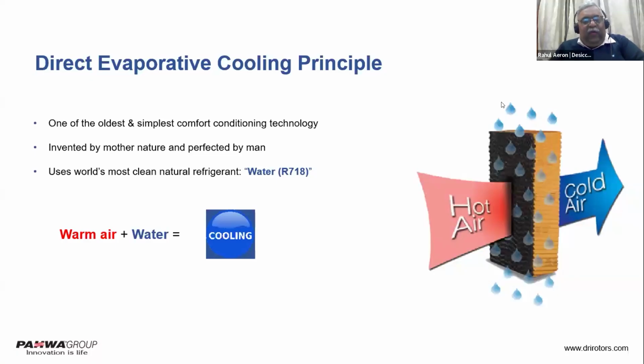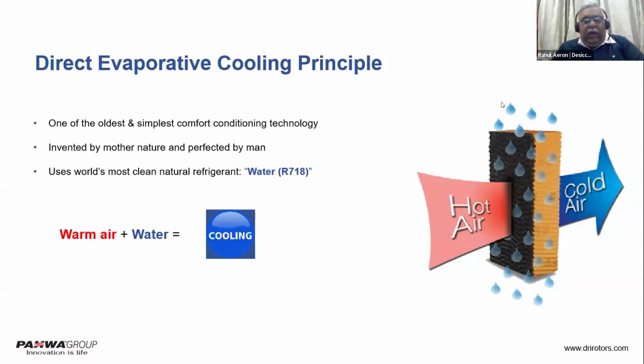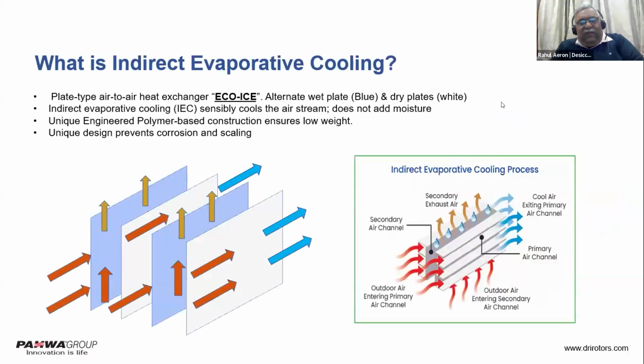So let me explain what direct cooling is. Direct evaporative cooling is, as I explained earlier, water being sprayed over the pad. The hot air comes in contact with water, the water evaporates, and it takes the heat from the air. So the air temperature goes down and some amount of moisture is added to the air. So there is no harmful refrigerant used. There is no artificial refrigerant used. It's the world's most natural, clean refrigerant, water, which is R718. Now, this is something which is new.